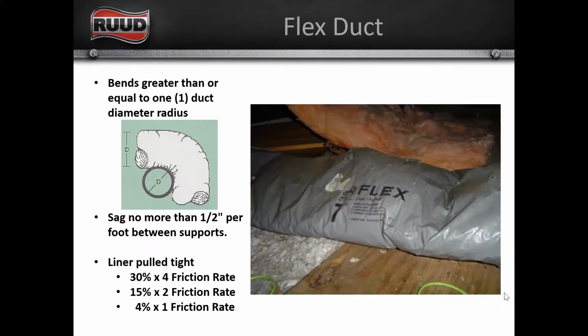And this is pretty common, right? You look up in somebody's attic, and 9 times out of 10, well, we'll give the benefit of the doubt and say 50% of the time you're going to see something like this. So when we're running flex, any turn or bend in that flex duct, you want that bend to be at least equal to the diameter, or the radius, of what you're running. So if it's a 7, you want that turn to at least be 7 inches round.